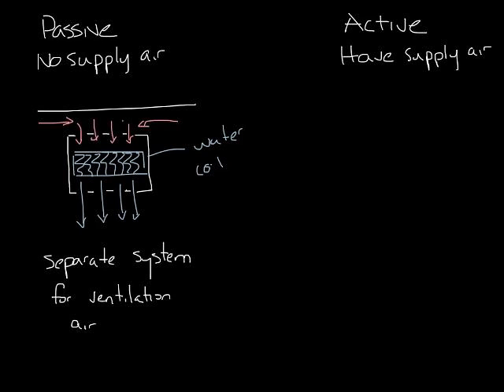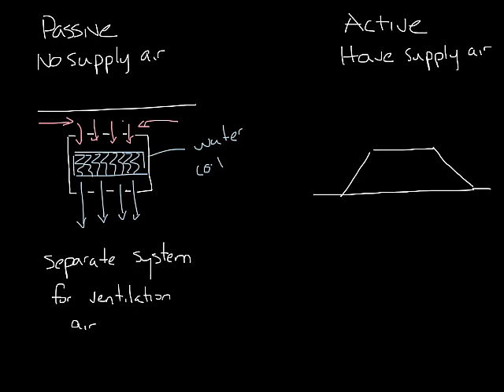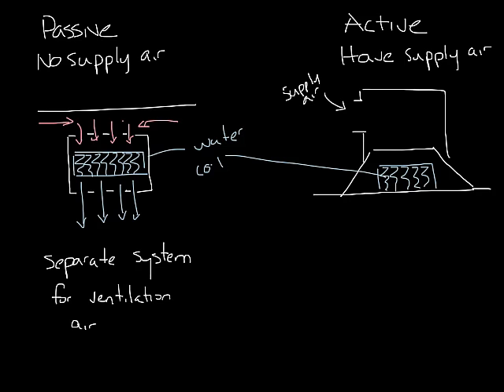Passive chilled beams are not as common as active chilled beams in the US, so let's move on to active chilled beams. Active chilled beams look a little bit like this. They mount flush with the ceiling. There's a plenum on top with a supply air inlet. And then the water coil is mounted here on the face. There are rows of nozzles along the inside of the plenum to allow air to go from the plenum into the cooling coil section of the unit.